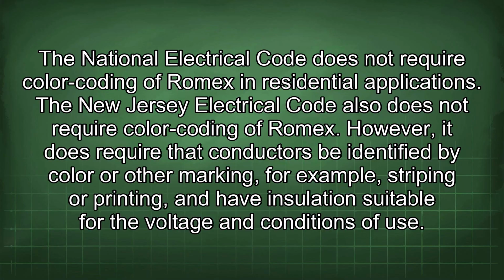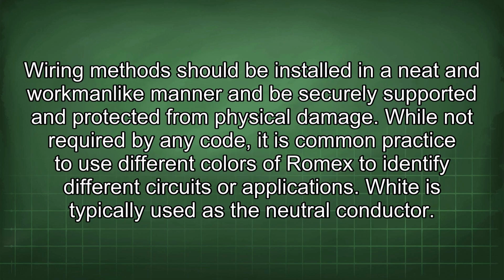The National Electrical Code does not require color coding of Romex in residential applications. The New Jersey Electrical Code also does not require color coding of Romex. However, it does require that conductors be identified by color or other marking, for example, striping or printing, and have insulation suitable for the voltage and conditions of use. Wiring methods should be installed in a neat and workmanlike manner and be securely supported and protected from physical damage.